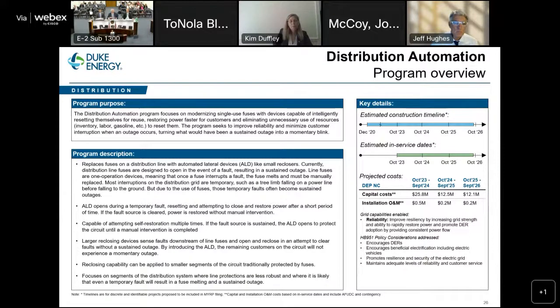You can think about the modern breaker panel in houses today, but you still have to go out to that panel and turn it off and back on to reset it. These devices do that on their own - no human intervention needed. If it is a permanent fault, it will operate and end up staying open, and there'll be a sustained outage, as it should be for a permanent fault. But temporary faults no longer cause sustained outages where these devices are deployed.